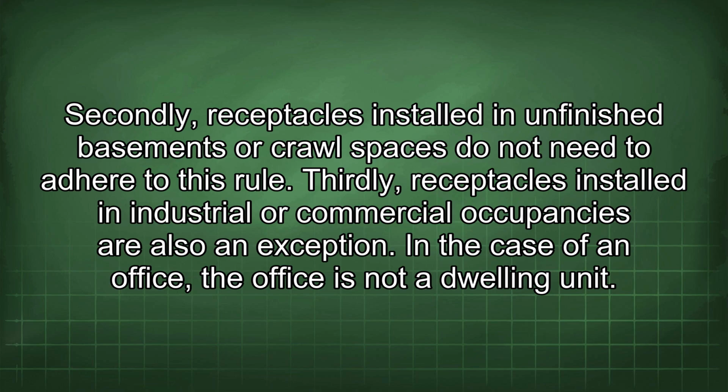Secondly, receptacles installed in unfinished basements or crawl spaces do not need to adhere to this rule. Thirdly, receptacles installed in industrial or commercial occupancies are also an exception. In the case of an office, the office is not a dwelling unit.